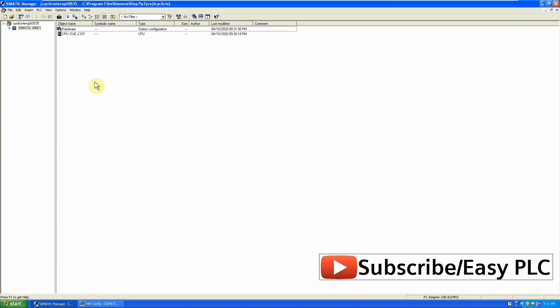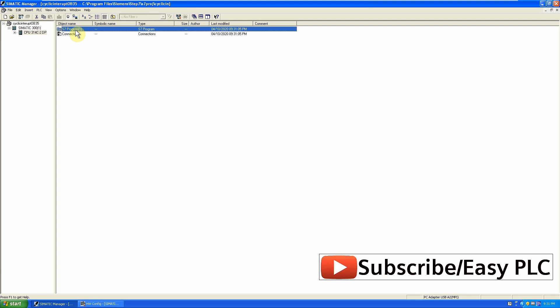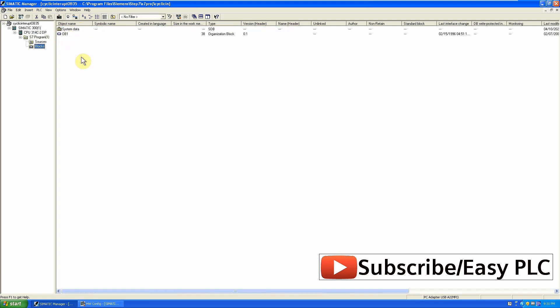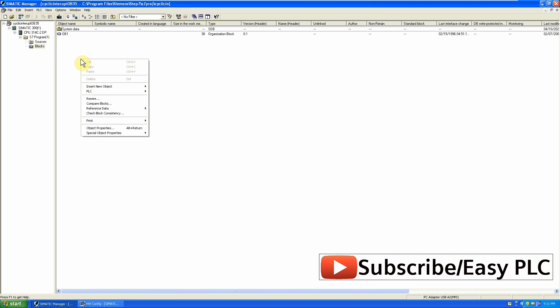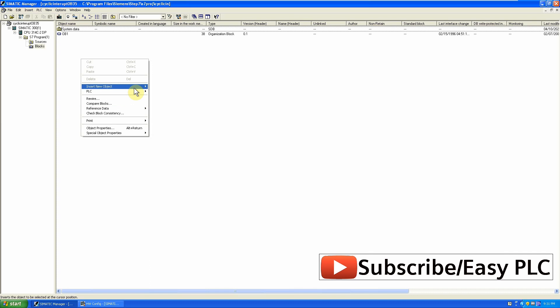Now we will go to the programming blocks and data organization block OB35. OB35 is cyclic interrupt with default 100 ms cycle type, which means it will be called automatically by process after every 100 ms interval.